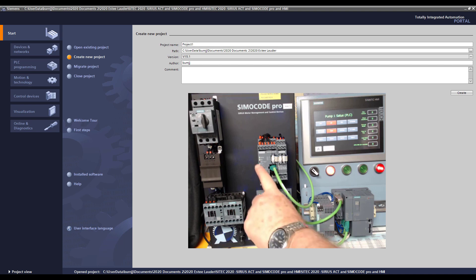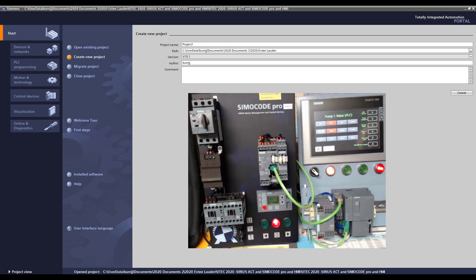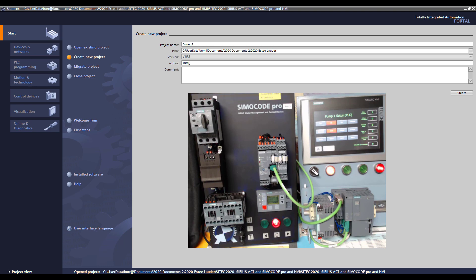As you can see I've got a fault condition on the demo here and I want to find out what was the cause of that fault. I'm going to do that by uploading the configuration of that particular SIMOCODE and then going online and having the SIMOCODE tell me the cause of the fault.